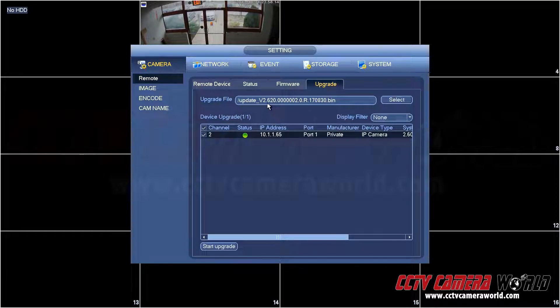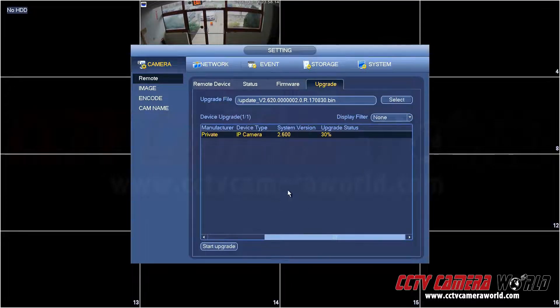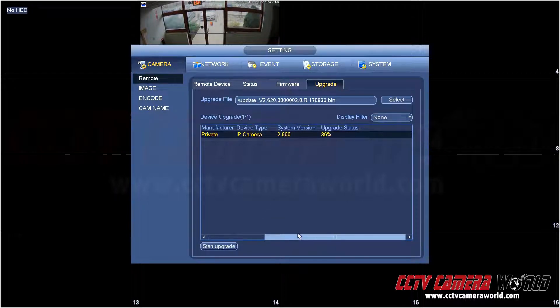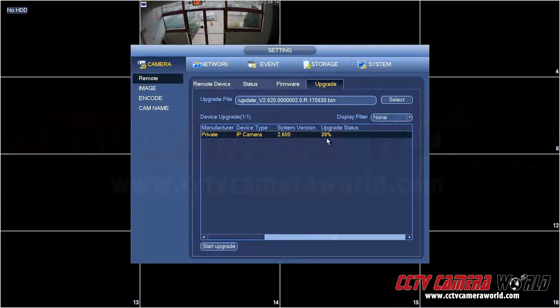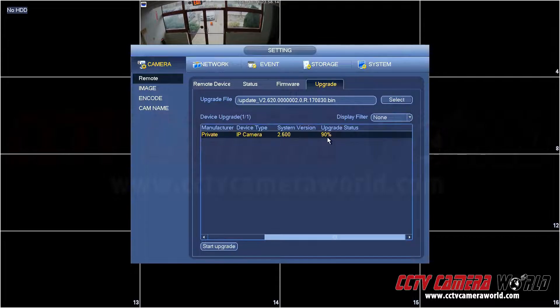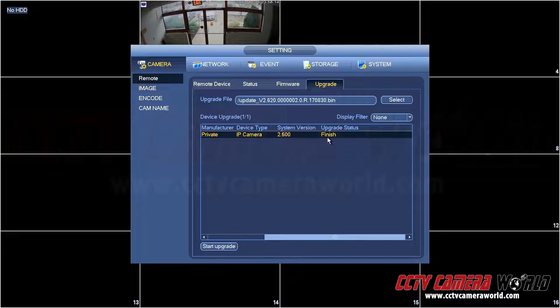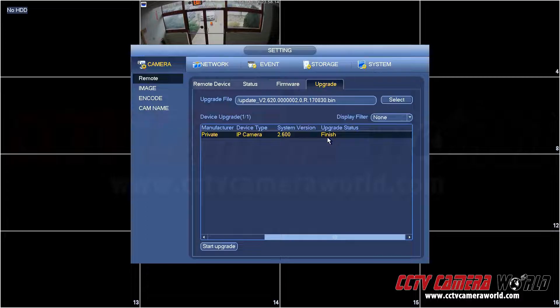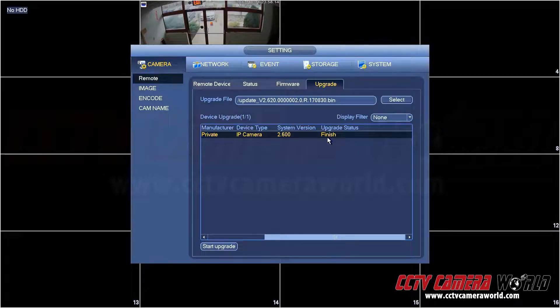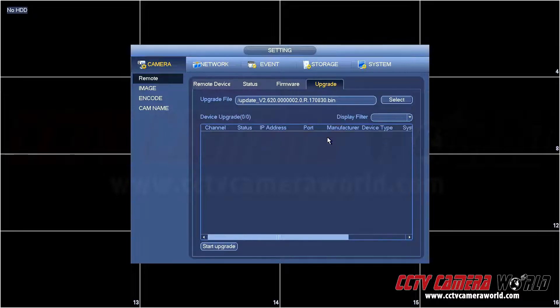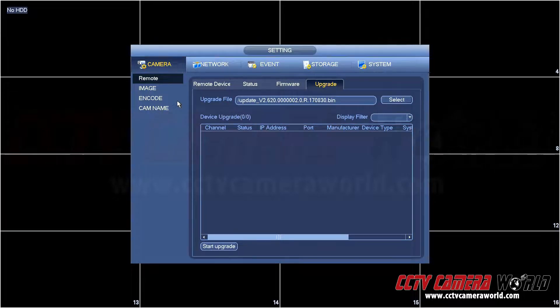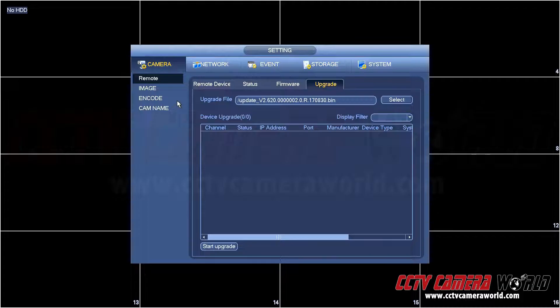The other way you will know if the firmware was successfully applied or not is the new firmware file has a version that's different. It's 2.6.2.0 and the old one has 2.60. If you navigate or move the browse bar to the right-hand side you'll see the current upgrade status. It says here upgrade status is finished. Give it some time for the camera to reboot. You'll see the video on the camera either go blank and reconnect depending on the camera firmware itself. Here we see it disconnect. It will take about one to two minutes for the camera to flash itself and reboot once the camera goes blank.